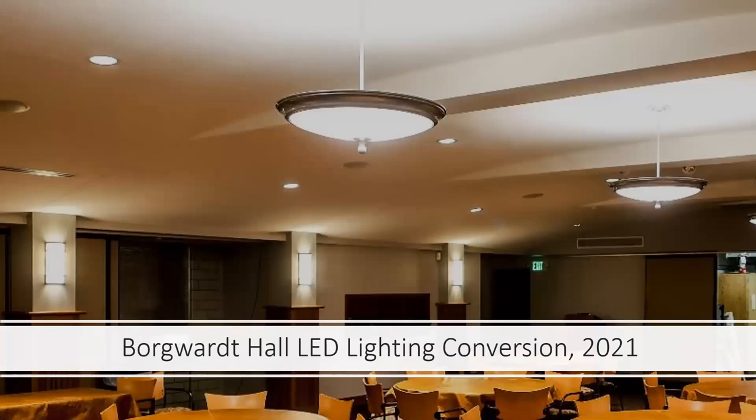Lighting is also a big part of Bethel's energy efficiency challenge. There are 1,150 lighting units inside and more than 50 more outdoors. Bethel's lighting has evolved over time, leaving a mixture of fluorescent, compact fluorescent, and halogen lights. Now more than 30% have been converted to advanced LED lighting, which is much more efficient and long-lasting. Directly swapping LED bulbs into older fixtures is often impossible. A careful conversion is necessary for satisfactory lighting.